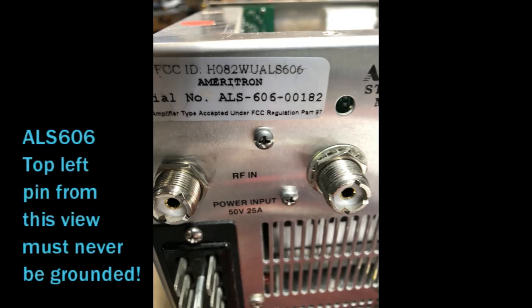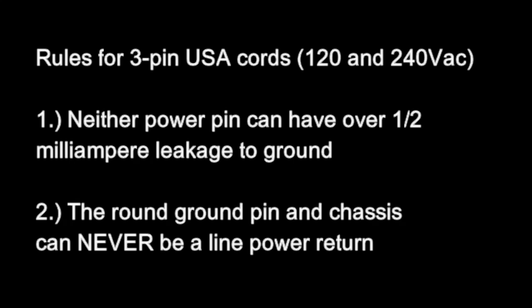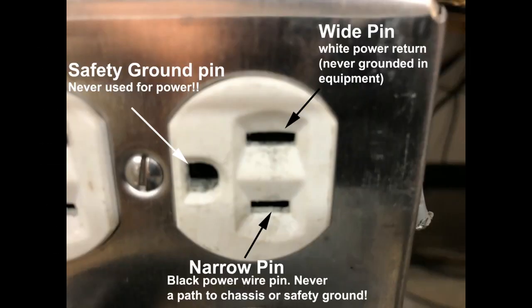The top connector pin from this rear view must never be grounded to the chassis. There are two critical rules using a 120 or 240 volt three wire circuit. Leakage from either line terminal of the chassis has to be less than a half a milliamp, and the round pin and chassis can never be used as a power line connection.